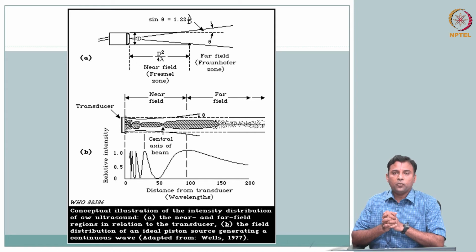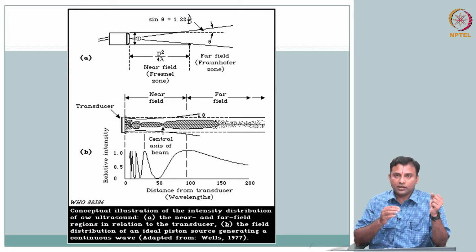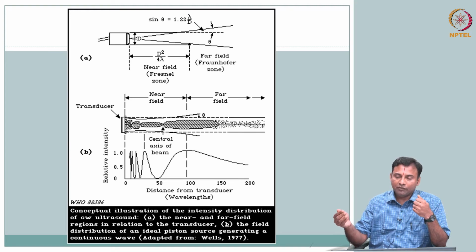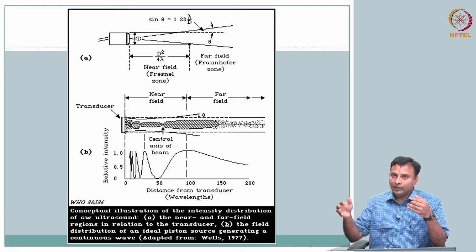Okay. So, what we have covered thus far is we started with instrumentation, and one of the major components in the instrumentation of an ultrasound system is your transducer, which acts, as we saw, as both a source, right. You could generate pressure waves as well as receive the pressure waves. So, on one side you can supply an electrical quantity, it creates a pressure wave, and on the reception we talked about how we will be using it in pulse echo mode, that is what is predominantly used for medical imaging applications.